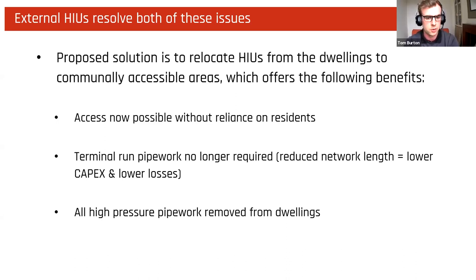So you're going from long terminal run pipework to needing at most half a meter of pipework from your multiple risers to each HIU. And the access is now possible without reliance on residents. All you need is the riser key, which the operator will have, so access is instant to 100% of HIUs. Another benefit, which I haven't touched on yet, is that you're also removing all high pressure pipework from your dwellings, and that opens up a whole lot of possibilities with regards to design from a hydraulic strategy as well.